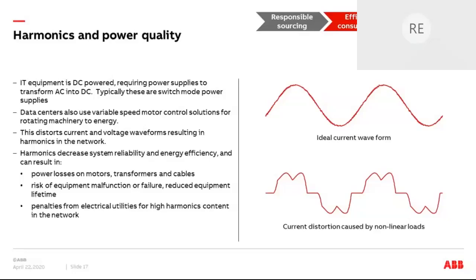As you can see by the bottom waveform, these power supplies distort the current. Once you distort the current, that adds heat and adds harmonics. Harmonics are basically frequencies outside the normal. The top waveform is a nice sine wave, but when you add switch mode power supplies, you start adding other frequencies. They reflect back in the system and you get the distortion seen below. This affects how your motors and transformers operate, affects the efficiency of your cables, and adds heat.